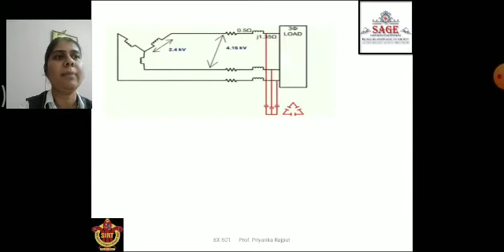You can see that with the transmission line, we connect a parallel capacitor for increasing the power factor. Its operation is that if an inductive load is connected to the transmission line, the power factor lags, because of the lagging of the load current. As a solution for this problem, a shunt capacitor is connected which draws current leading the source voltage, and the result is a better power factor. Low power factor causes poor voltage regulation.